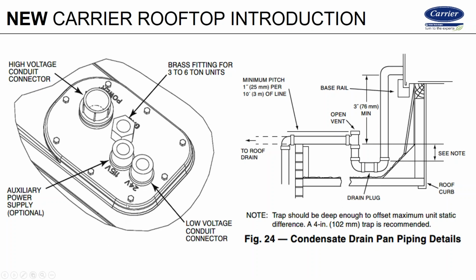This little area is raised up about 3/8 of an inch off the rest of the deck of the condenser area. So if you get water, which you will from snow and rain as it comes through the condenser fan and the coils, that water will run off the deck and it won't get high enough to get into any of these connections, which should all be seal tight, properly gasketed connections. But again, you can bring power in, you can bring gas in, you can bring a convenience outlet in, control wire in through this area. So that's still an option.